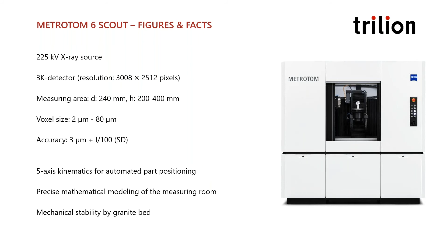Just some of the facts and figures. We do have a 225 kilovolt source, which is middle of the line. This can measure any plastic, pretty much any aluminum, and it can get up to some stainless steels and nickels and titaniums, just depending on your application and the size of the part. Just for the sake of time here, we'll skip through a few of these.